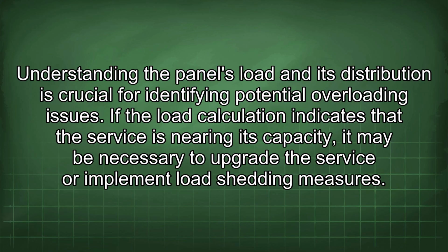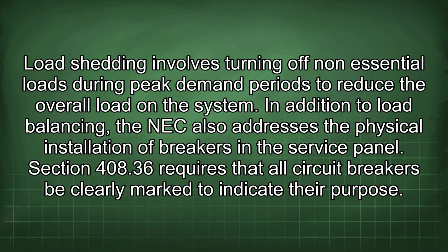If the load calculation indicates that the service is nearing its capacity, it may be necessary to upgrade the service or implement load shedding measures. Load shedding involves turning off non-essential loads during peak demand periods to reduce the overall load in the system. In addition to load balancing, the NEC also addresses the physical installation of breakers in the service panel.